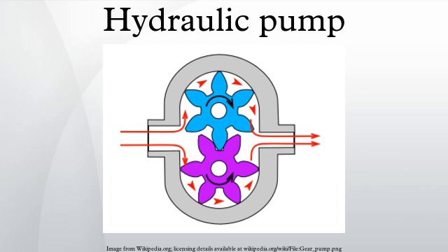Multi-pump assembly. In a hydraulic installation, one pump can serve several cylinders and motors. However, in that case a constant pressure system is required and the system always needs full power. It is more economic to give each cylinder and motor its own pump. In that case, multi-pump assemblies can be used. Gear pumps are often supplied as multi-pumps. The different chambers are mounted in one body or built together.